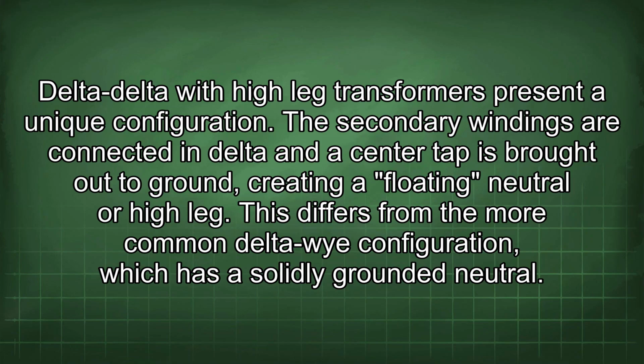Delta-delta with high leg transformers present a unique configuration. The secondary windings are connected in delta and a center tap is brought out to ground, creating a floating neutral or high leg. This differs from the more common delta-Y configuration, which has a solidly grounded neutral.